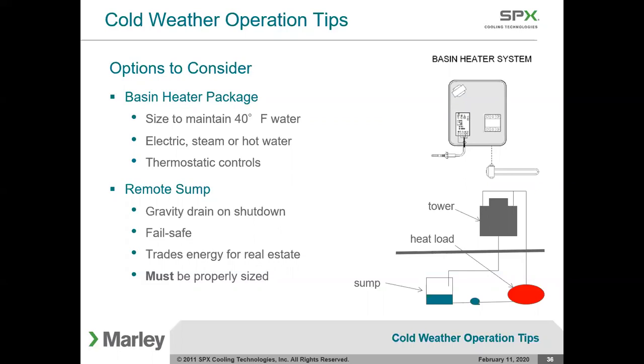We could have a remote sump. The tower could be set up on the roof, and the sump could actually be inside. You see plants that just have big tanks inside that serve as the sump to the cooling tower. So the pump returns the water up on top, and it falls down through the tower, and then it's piped back into the sump or the tank inside. As long as you condition the building inside, that's pretty much hard to freeze up. Again, you can freeze up the tower, but you're not going to freeze up the sump. So that's a pretty good idea.